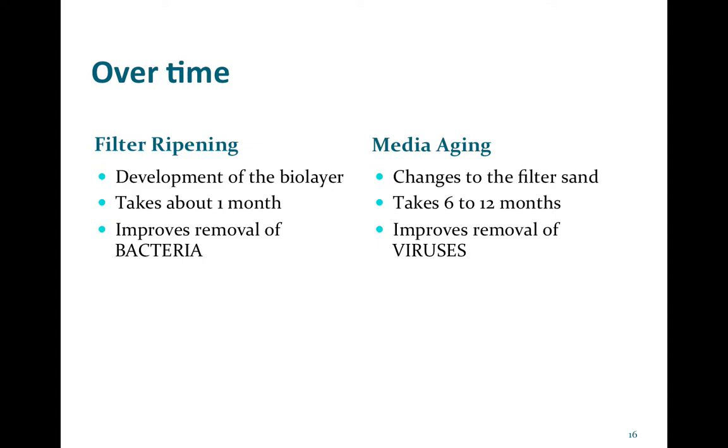The second process we'll refer to as media aging. It's completely different. It takes much longer, 6 months to a year, and has to do with mineral deposition and biological communities deep within the filter bed. This improves the removal of viruses within the filter.